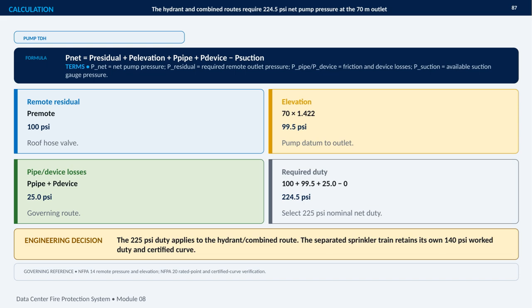net pump pressure. The engineering decision is to select a 225 psi nominal net duty. That duty applies specifically to the hydrant and combined route. The separated sprinkler train is not replaced by this value. It retains its own 140 psi work duty and certified pump curve.